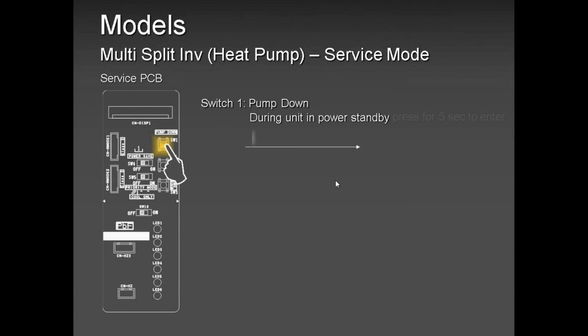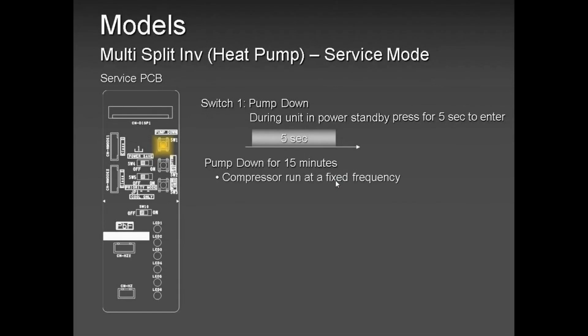Now let's talk about this PCB, okay? This is the panel outside. This is 1, 2, 3, 4, A, B, C, D. This is a 4-zone outdoor unit. So that's your incoming power. That's your zone A, zone B, zone C. Even though we're talking about a 5-zone, the 5 and the 4-zone PCBs and the terminal blocks will look the same.